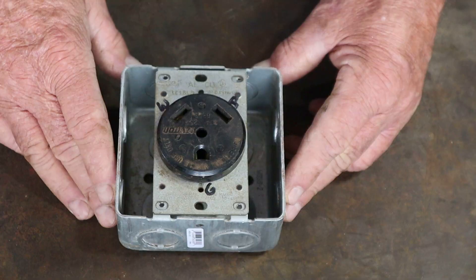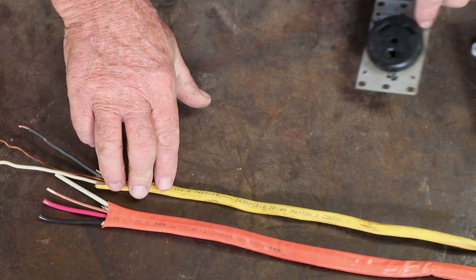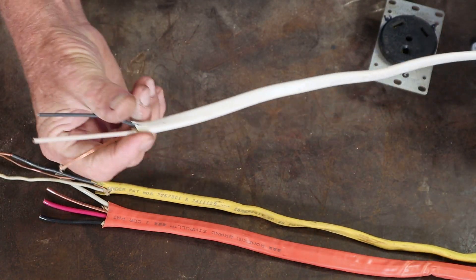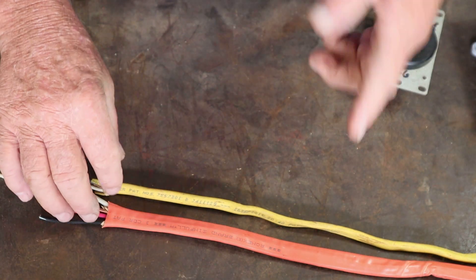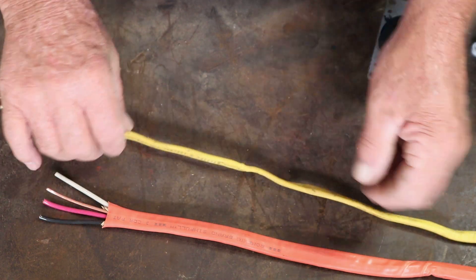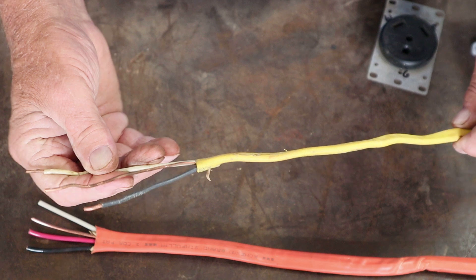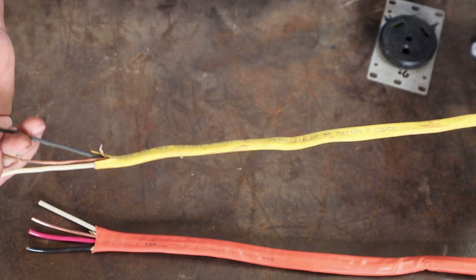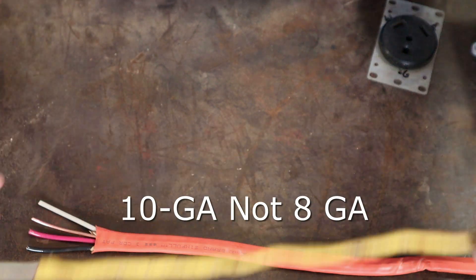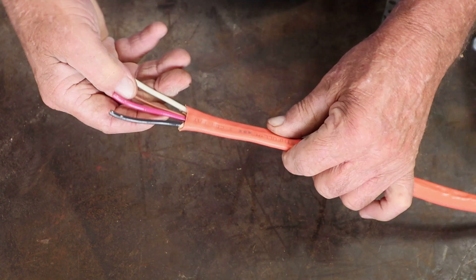To determine which wire you need for this 30-amp circuit, you surely could not use a 14-2 — it's just not heavy enough, so don't gamble with the possibility of causing a fire or electrical issues. Next up is the 12-2; although it's a little heavier and will carry more current, it would not be my go-to choice. I would highly recommend going up to 8-gauge wire.